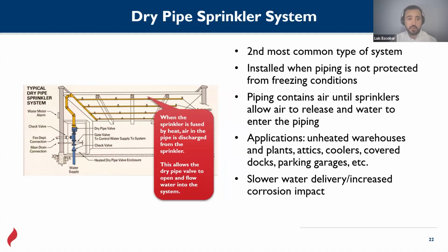When there's a fire, we know the sprinkler opens, and then all this air goes out of the system, and when the water reaches the open sprinkler, the water starts falling down, right? So the most important characteristic of this system is there's air in the pipes upstream, and when there's a fire, a sprinkler opens. Once all the air is released, then the water starts releasing.